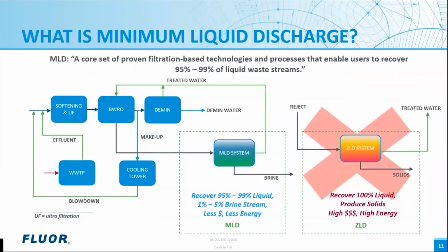Now let us start by defining the term minimum liquid discharge, which is typically defined as a core set of proven technologies and processes that enable users to recover 95 to 99% of the liquid waste streams that may be otherwise wasted. Now, as you well know, water treatment systems produce a waste or a reject stream during the treatment process, which contains a certain level of contaminants. Such a waste stream can be anywhere from 25 to 50% of the total water supplied to the treatment system.